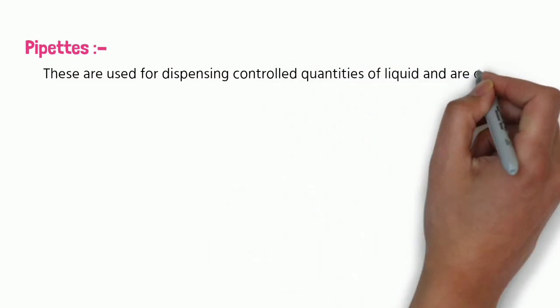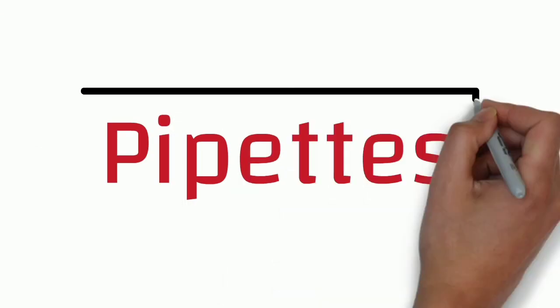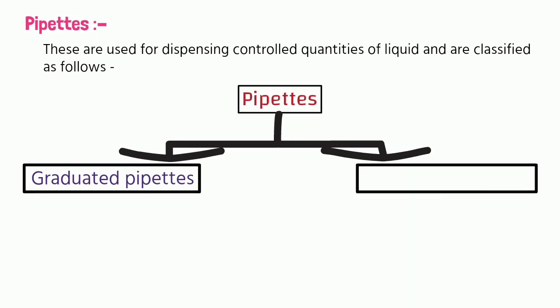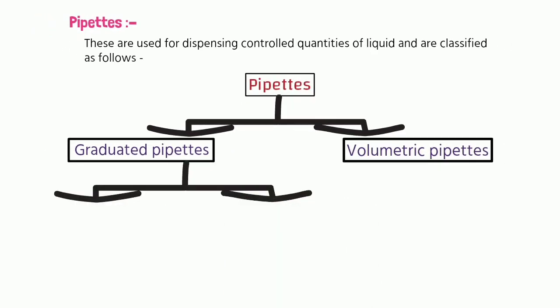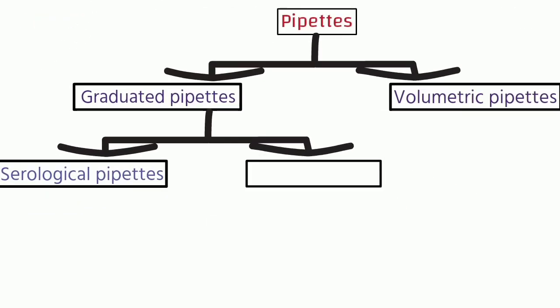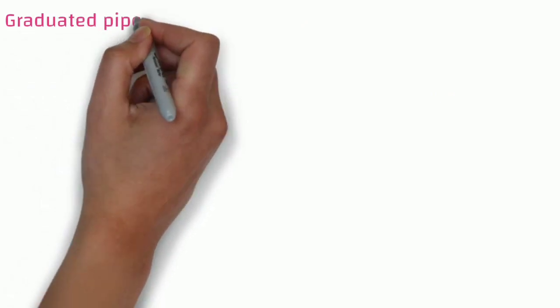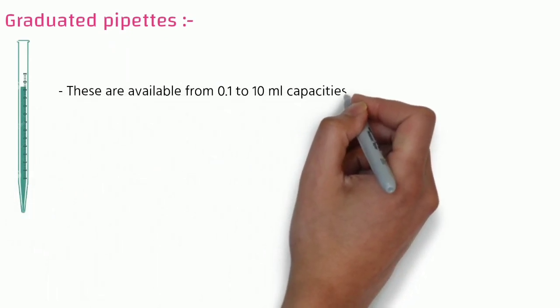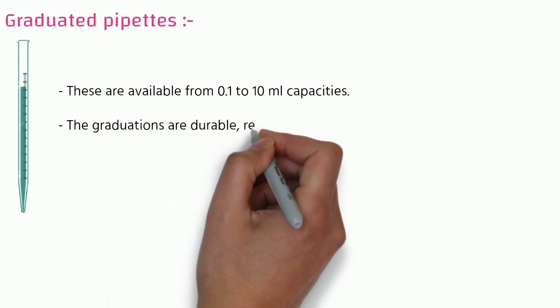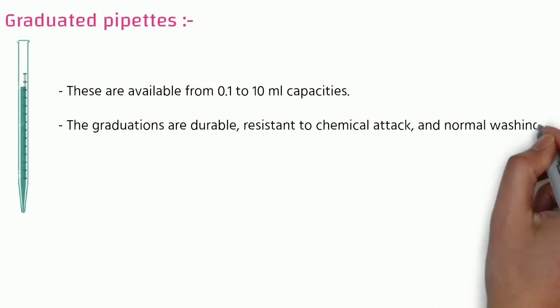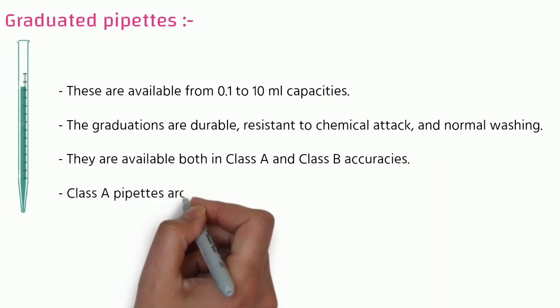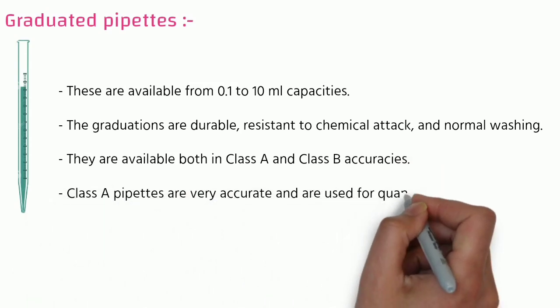Pipettes are used for dispensing controlled quantities of liquid and are classified as follows. You can see some types of pipettes in this picture: graduated pipettes and volumetric pipettes. In graduated pipettes there are two types: serological pipettes and Mohr's pipette. Graduated pipettes are available from 0.1 to 10 ml capacity. The graduations are durable and resistant to chemical attack and normal washing. They are available in both Class A and Class B accuracies. Class A pipettes are very accurate and are used for quantitative determination.